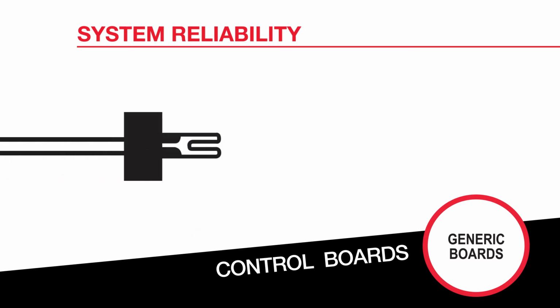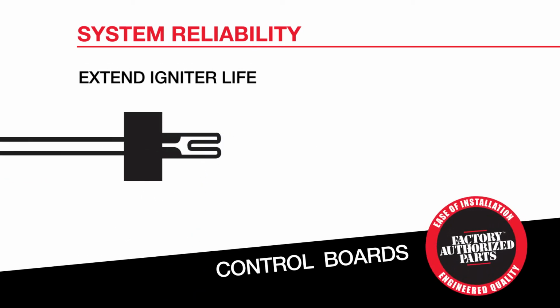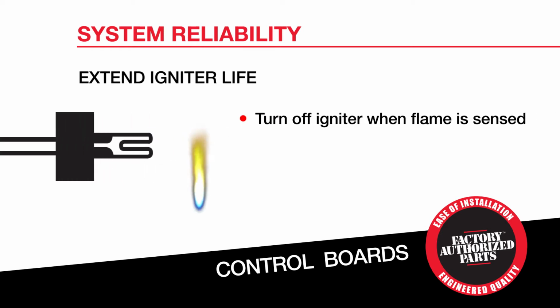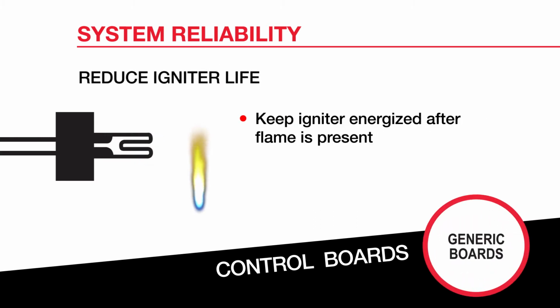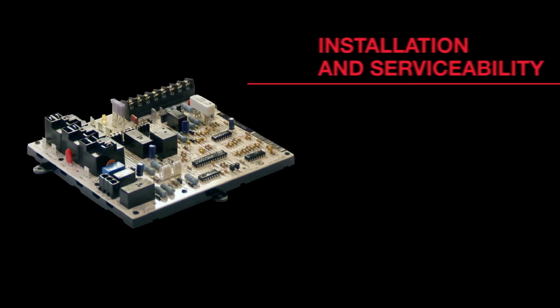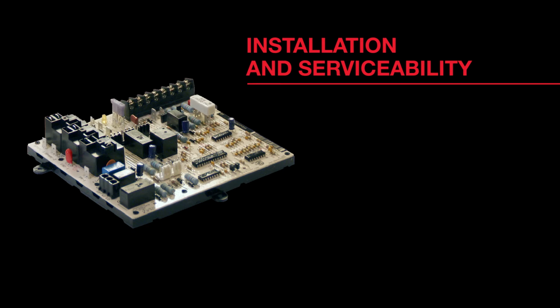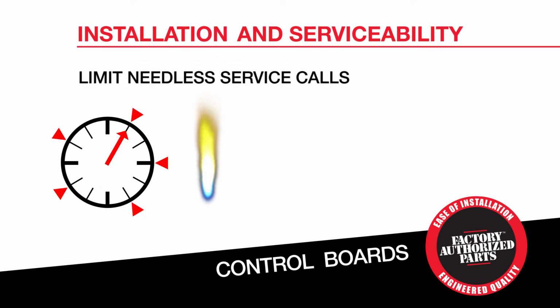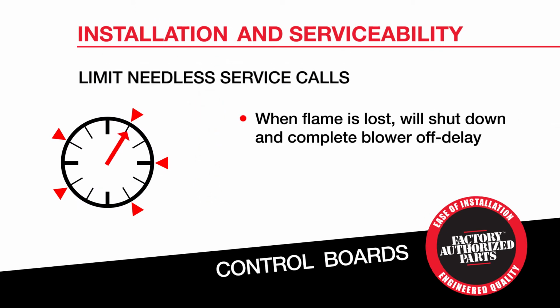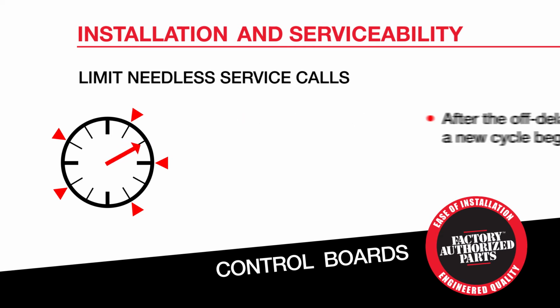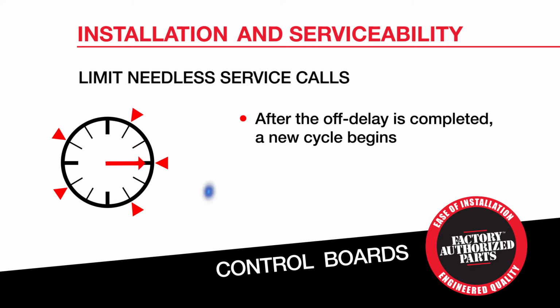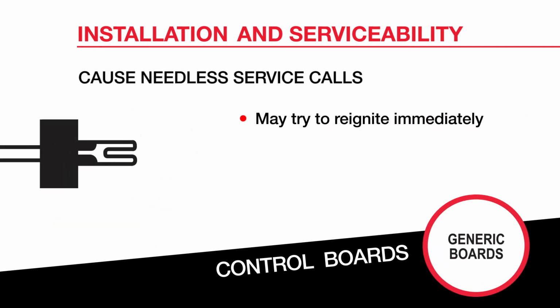And speaking of component lifespans, factory authorized parts control boards will also extend igniter life by turning off the igniter the moment a flame is sensed. Some generic boards keep the igniter energized even after the flame is present. This creates additional wear on the igniter. If you're looking for ease of installation and serviceability, factory authorized parts control boards are the best choice. You'll limit needless service calls because when the flame is lost, a factory authorized parts board will shut down and complete the blower off delay. After the off delay is completed, a new heat cycle will begin. Generic boards may try to reignite immediately, leading to a needless service call.